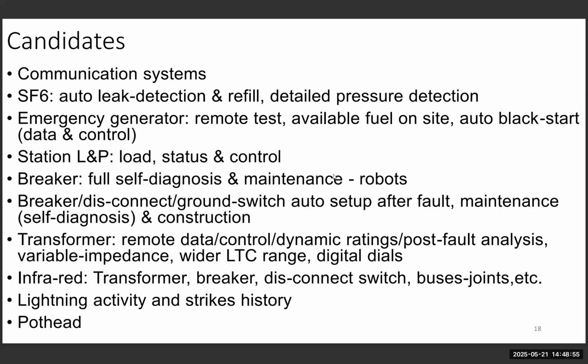The emergency generator, the example I gave: either it physically exists, and if you know anything about generators, it takes a long time to set up and test, a lot of money, and a lot of people get involved. But if it's already connected, you send the signal and it runs, and you can see from the SCADA whether it works or not. The station light and power, as we spoke about before: most utilities have at least two of them, supplied from two different circuits. That's very important.